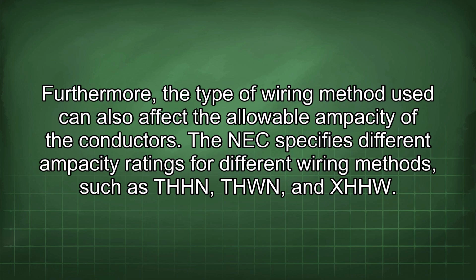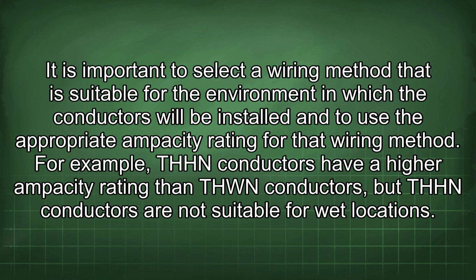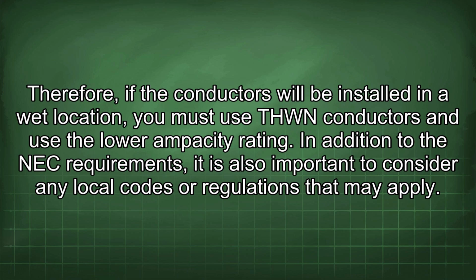Furthermore, the type of wiring method used can also affect the allowable ampacity of the conductors. The NEC specifies different ampacity ratings for different wiring methods such as THHN, THWN, and XHHW. It is important to select a wiring method that is suitable for the environment in which the conductors will be installed and to use the appropriate ampacity rating for that wiring method. For example, THHN conductors have a higher ampacity rating than THWN conductors, but THHN conductors are not suitable for wet locations.